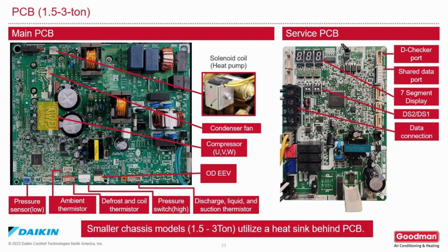Please keep in mind that the voltage between U and V, V and W, W and U should be equal and balanced. It really doesn't matter what that voltage is, as long as it's the same between all terminals. Also, it is important to know that that is a simulated AC voltage made of DC. You will set your meter to read AC. Be extra careful when you're reading the compressor voltage. Even though it's reading as AC on your meter, it's made up of DC, which means DC could arc together between terminals when testing, which would damage the circuit board and quite possibly your meter.